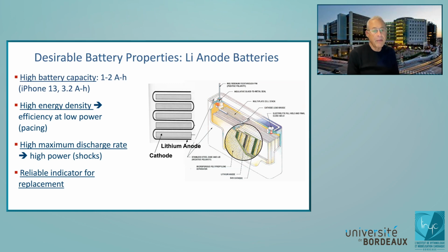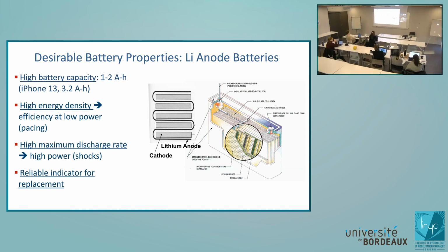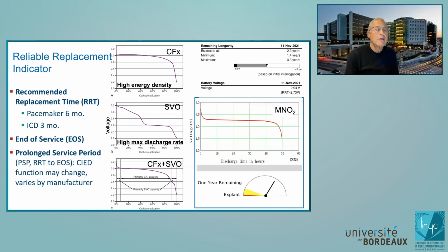And lastly, we want a battery that has some reliable way to tell us when it goes belly up. It's not like we look for our flashlight and can't turn it on, and say oh, it's time to change the batteries. That's obviously not a good solution for a pacemaker dependent patient. So replacement indicators for pacemakers, by international standard, are supposed to give you 6 months warning, and for defibrillators 3 months warning before they go to what we call end of service performance, which means some of the more optional but not life-sustaining features just don't work anymore.